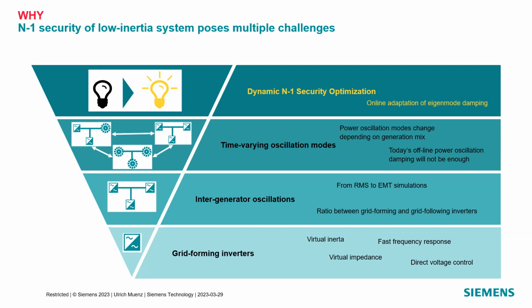We saw it in Jean's presentation: before the outage of the generator, the system was stable, there were no 90 Hertz oscillations. Then the poles moved to the imaginary axis after one generator was taken out. That was one extreme case. But in a large interconnected system, you'd expect this to happen just from normal redispatching of generation units, and operators have to prepare for these time-varying oscillation modes.